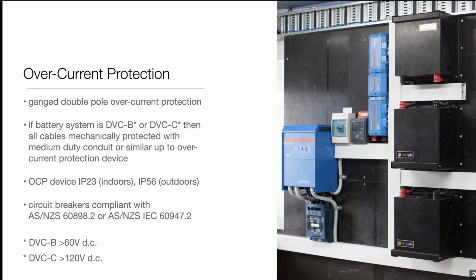Now, DVC B and C are deemed to be equivalent to LV as defined in AS/NZS 3000. So once you go over 60 volts on your battery, you've now got something that needs to have double insulated cables. It needs to be protected from touch to IP2X. You can't touch it with a test finger. It needs to be installed by a licensed electrician in Australia and New Zealand. So that is a big change from our previous standards, where we allowed you to go to 120 volts on a battery system without license requirements or double insulation.